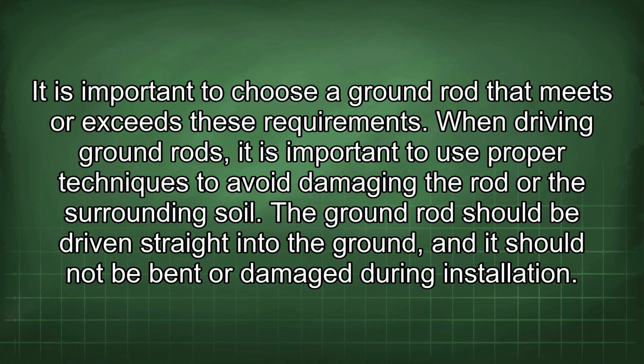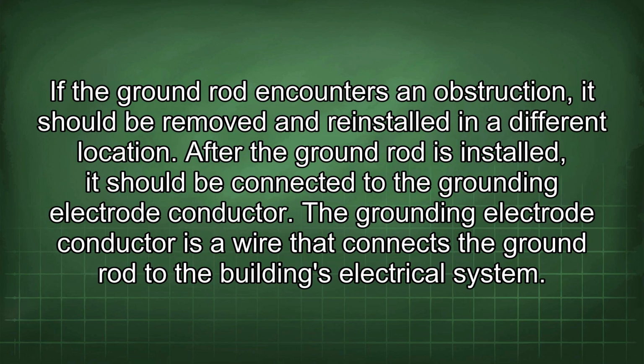When driving ground rods, it is important to use proper techniques to avoid damaging the rod or the surrounding soil. The ground rod should be driven straight into the ground, and it should not be bent or damaged during installation. If the ground rod encounters an obstruction, it should be removed and reinstalled in a different location.